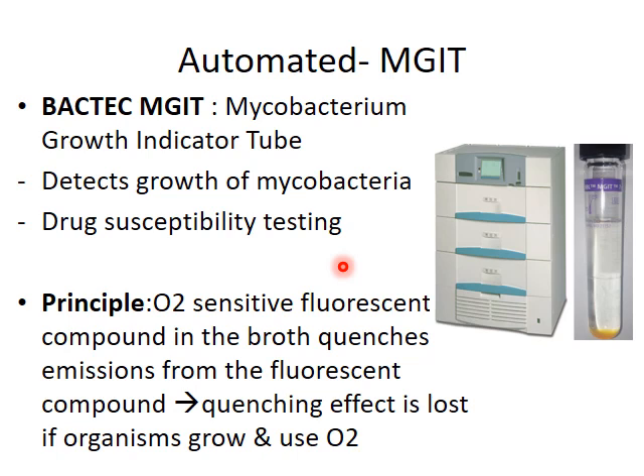We shall see the automated system in detail. One of the automated systems available is BACTEC MGIT, which stands for Mycobacterium Growth Indicator Tube. It detects the growth of mycobacterium and also performs drug susceptibility testing. The principle behind this method is that the media uses an oxygen-sensitive fluorescent compound dissolved in the broth. Initially, dissolved oxygen quenches the emissions from the fluorescent compound. Later, actively respiring microorganisms consume the oxygen, the quenching effect is lost, and fluorescence is detected by the machine, flagging the sample as positive.